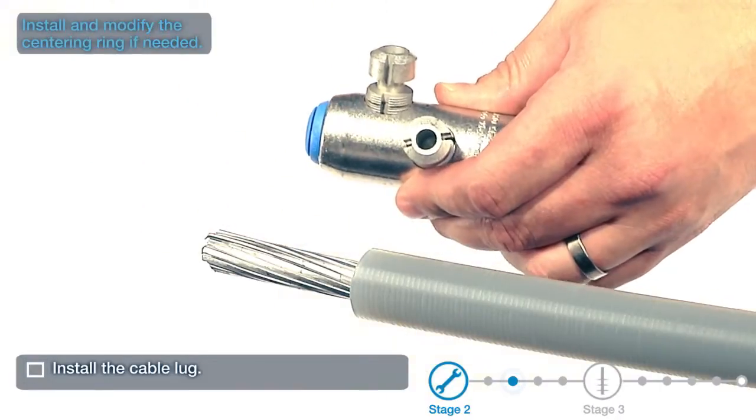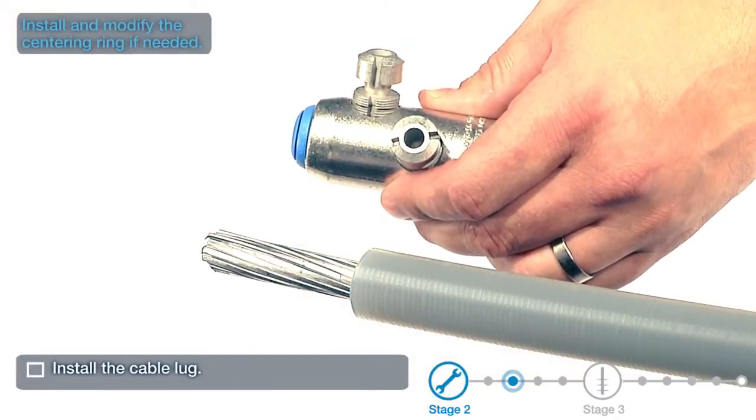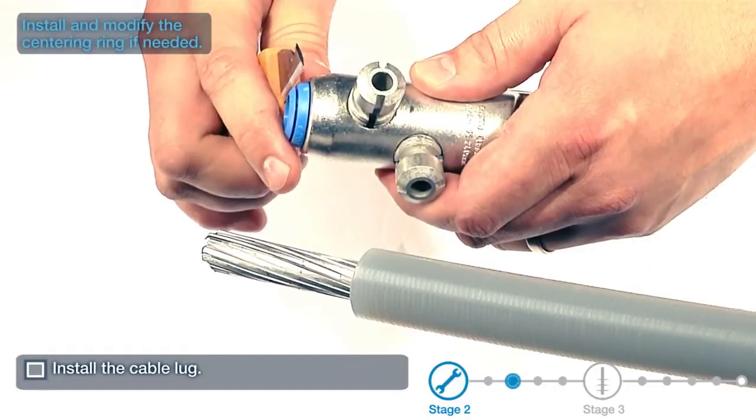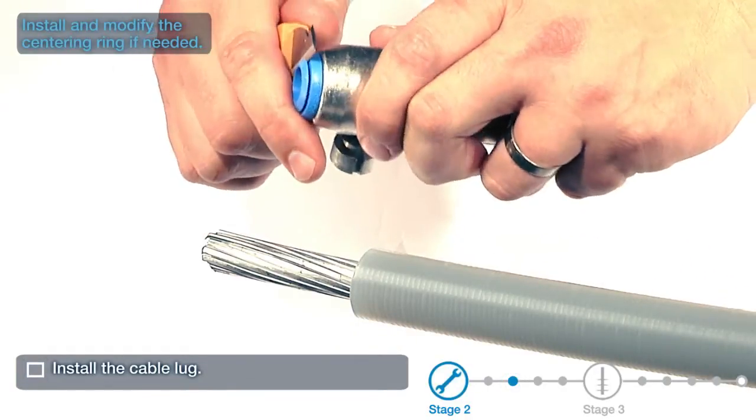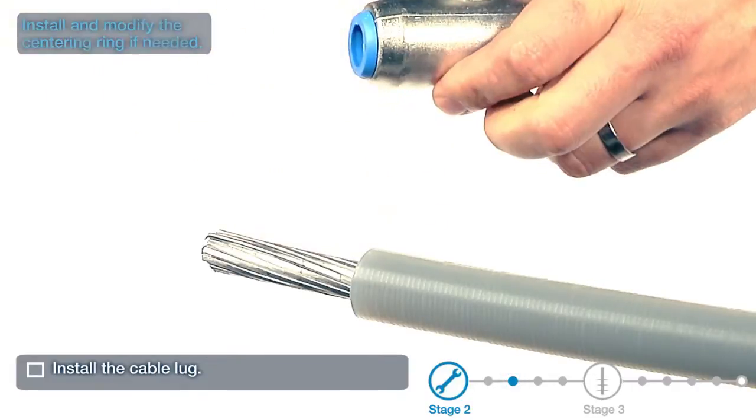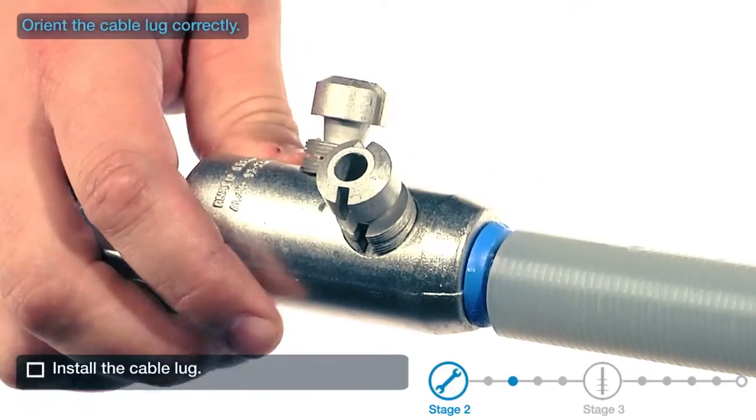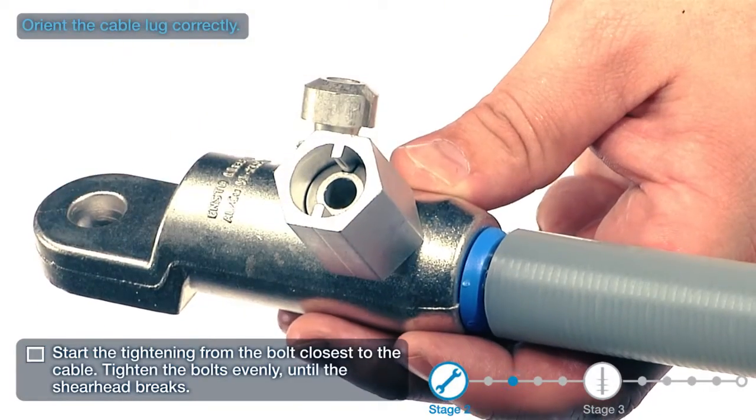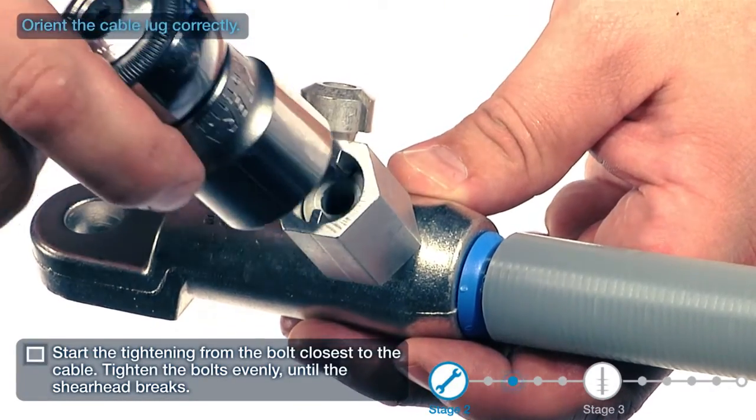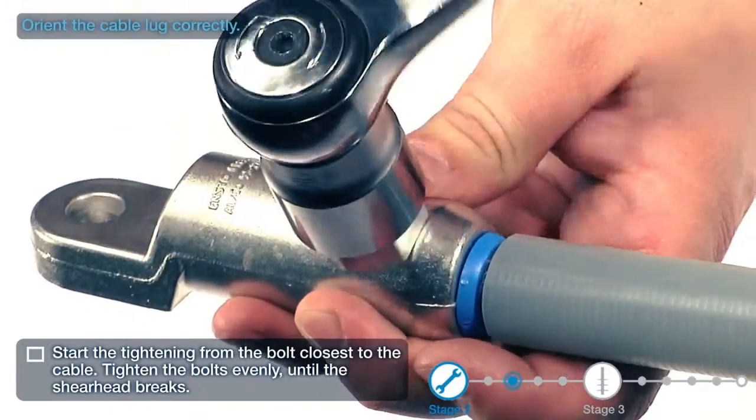Install and modify the centering ring if needed. Orient the cable lug correctly. Start tightening from the bolt closest to the cable. Tighten the bolts evenly until the shear head breaks.